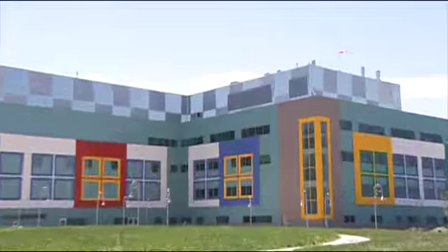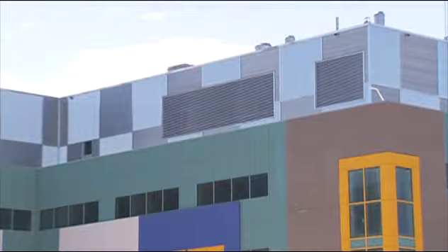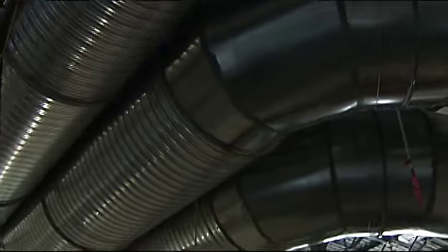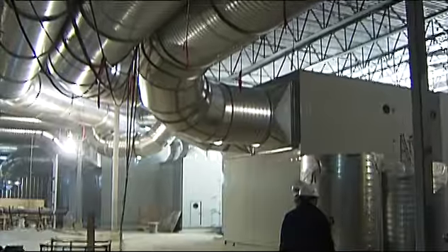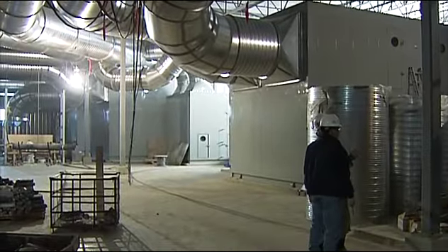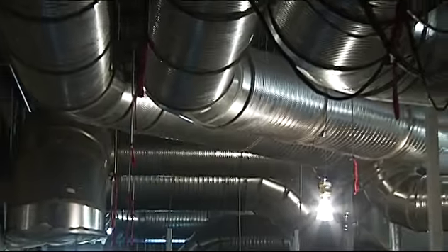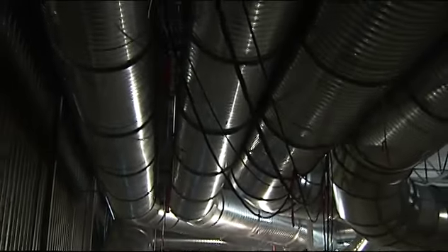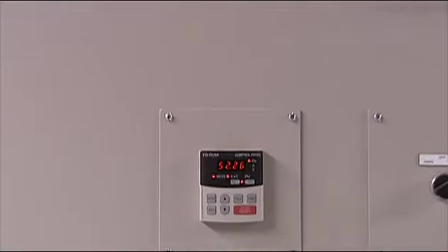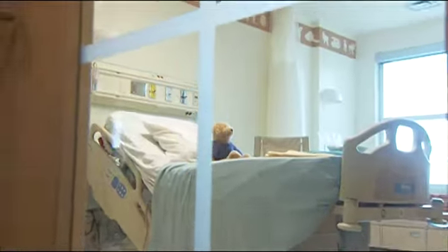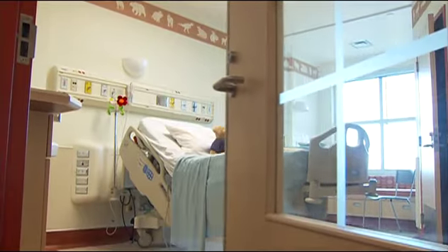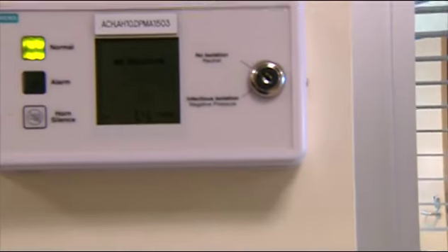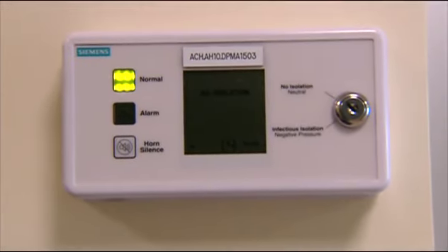It's all controlled here on the top floor in what we call the penthouse. This area at the top of the hospital controls air and water flow throughout the building. We have 28 air handling units that supply air to this building. We've zoned the air handling units so that we can isolate certain parts of the building, so when a door is opened in an infectious room anywhere in the hospital, the air pressure can be controlled so that only fresh outside air moves in, and infectious inside air is filtered as it moves out.